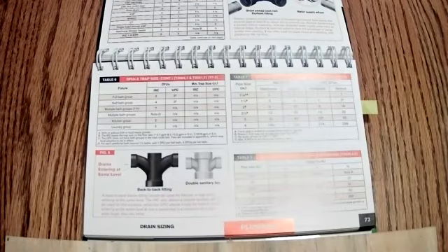So now again, you got to make sure that whenever you're using some of these items like the IRC drainage fixture units on a building drain and branches, okay, the pipe size 1.5 inches, the slope needs to be, it's not available. Okay, note A down there, what does it say? It says 1.5 inch horizontal branches and building drains are limited to a pump fixture unit, including food waste disposals and grinders, and a 2-inch non-pump fixtures. And B, drains less than 3 inches may not be used to receive discharge from water closets. So we're never going to use a drain line that's less than 3 inches on a water closet.